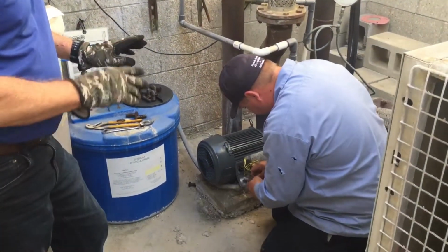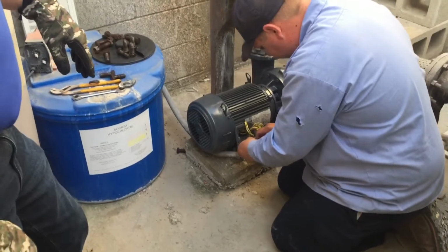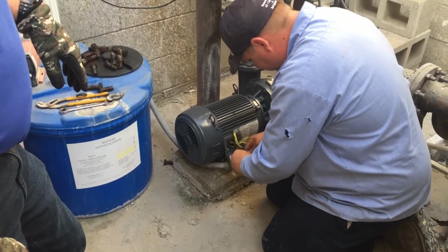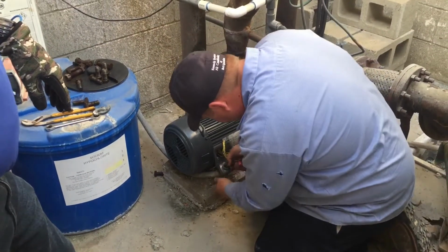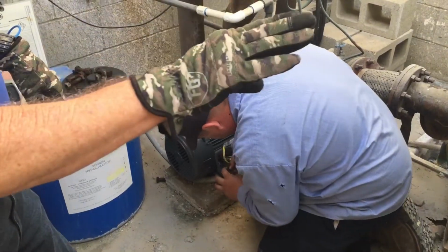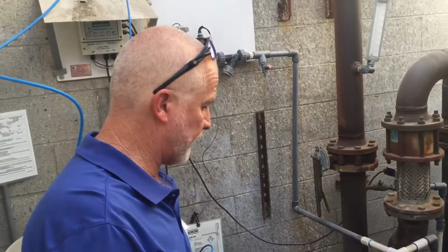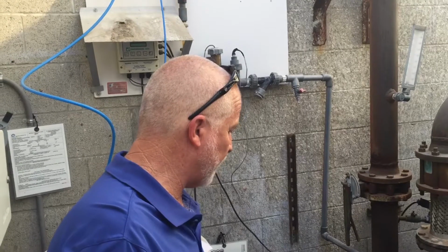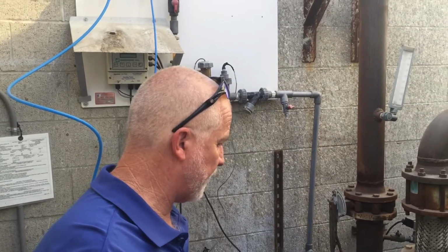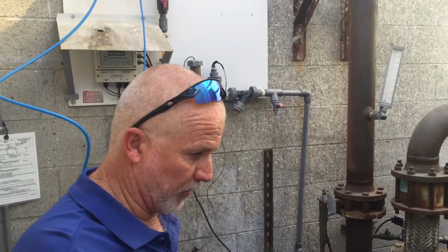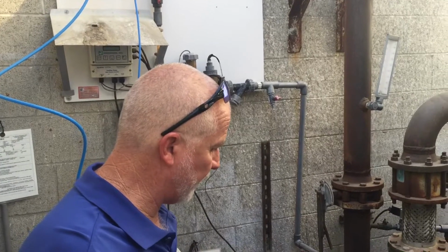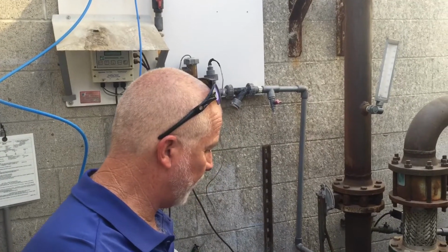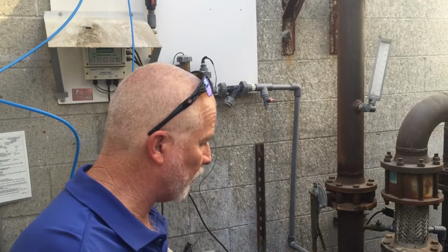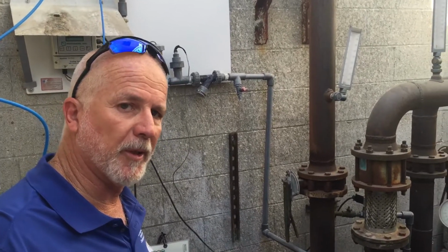Absolutely, we're going to order the same exact Peerless pump. My project manager has already got Peerless working on it, he's been in touch with Baltimore Aircoil, the manufacturer, got all the specs, and they're putting together a quote for us and building us a spare pump that we can store in the chiller room. Literally, if this were to happen again, once we're on site, within an hour we can have this pump changed out and the backup pump installed.